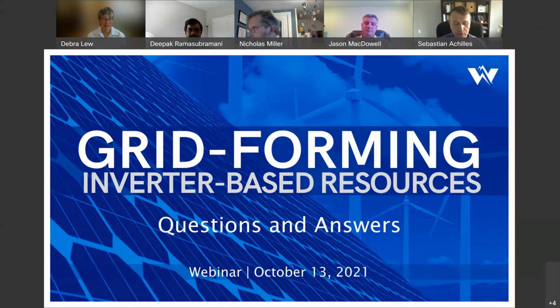On the first question of how the inverter-based resource identifies when to provide additional power, these control actions are intended to be really fast, so this can only be done based on signals the converter control is receiving. The feedback signals are all the information used to make those decisions. The intrinsic algorithm of grid forming control is more responsive to variations in the angle of the voltage than grid following, but the information is all based on voltage and current measurements. It's a control response, just controlled differently to make it faster in grid forming compared to grid following.